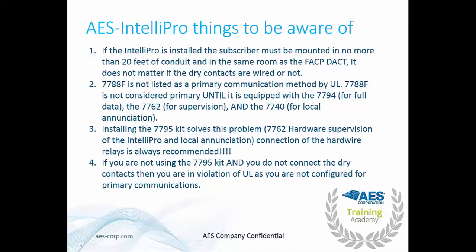The 7788F is not listed as a primary communication method by UL. The 7788F is not considered primary until it is equipped with the IntelliPro — the 7794, the 7762 which provides hardware supervision, and the 7740 which is for local annunciation. All of this is included in the 7795 kit, which includes the 7762 for hardware supervision and local annunciation with the 7740.